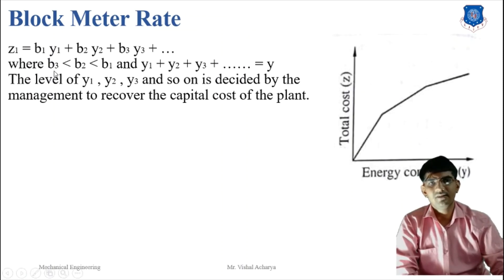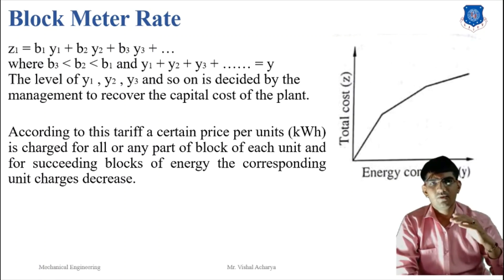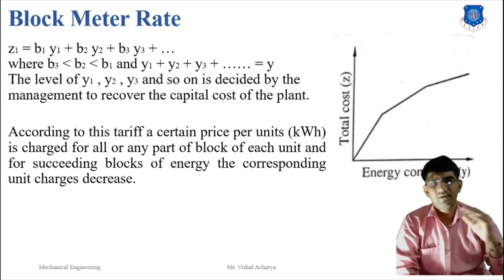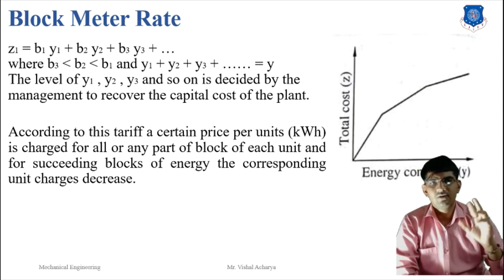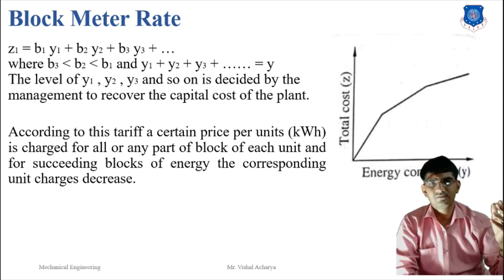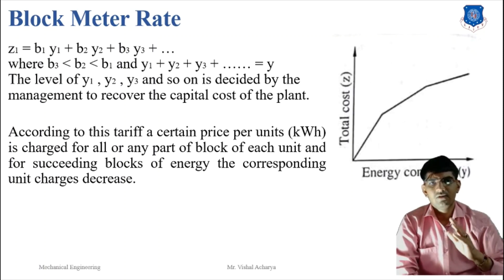Next is the block meter rate. Here the energy is divided into blocks Y1, Y2, Y3, with total energy consumption B1×Y1, B2×Y2, B3×Y3. The same price per unit is charged for each part of a block, and for each succeeding block the unit charge decreases. For example, if you use 100 units the price is 5 rupees per unit; for 100 to 200 units it is 4 rupees; and above 300 units the price per unit drops to 2.5 or 3 rupees. As energy usage increases, the per-unit price decreases.